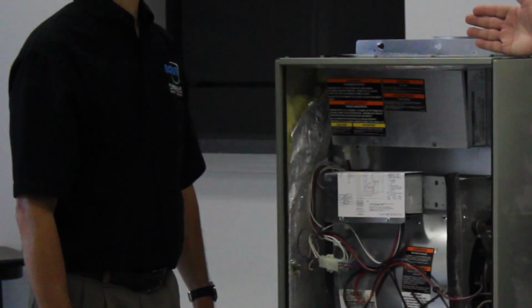What happens when that pipe gets clogged with debris, mold, or mildew? A plugged or clogged drain line is one of the number one service call reasons. In most cases there's a safety switch that shuts the equipment off before water overflows the drain pan and damages the floors or contents of the house. At Aqua, we have contract plans where twice a year, every six months, we come out to flush that drain line and wash the coil. These preventative maintenance items are intended to cut down on unnecessary service calls or those late-night interruptions that make your home uncomfortable.